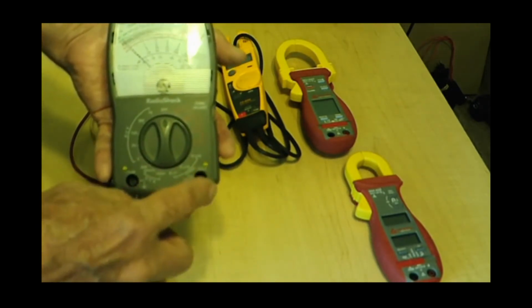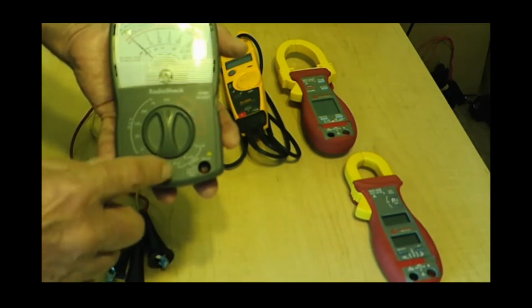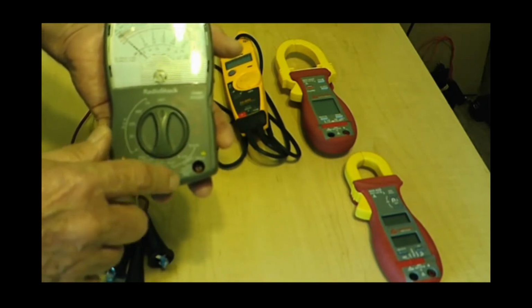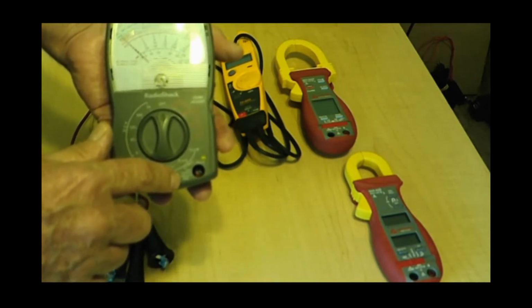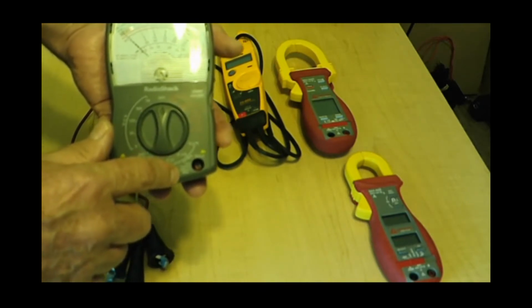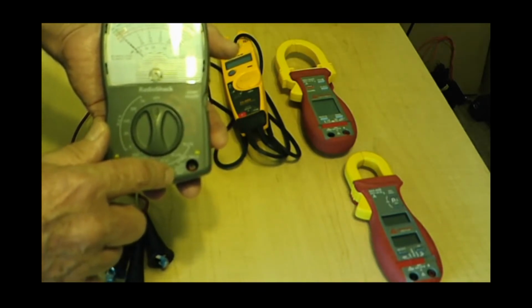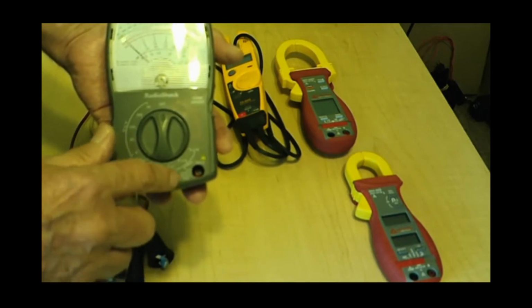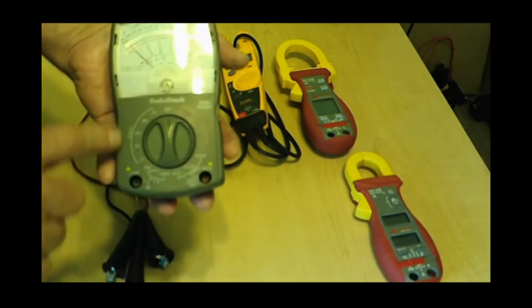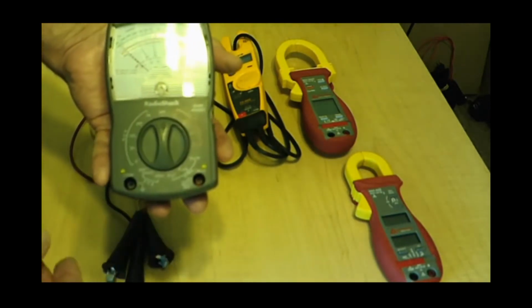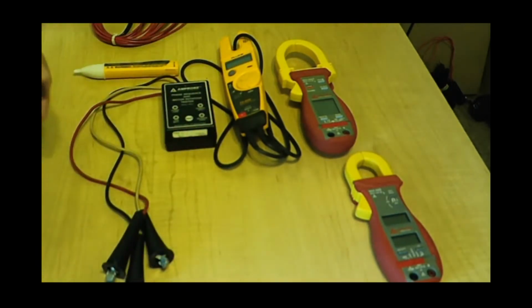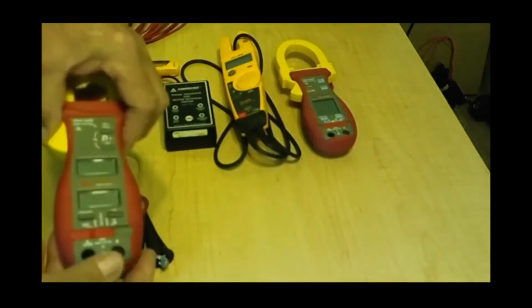You only have two terminals for inputs here. This one is category 2. It's 1,000 volts AC, 250 milliamps max. So the rating's right on there. If you exceed those ratings, this meter can explode. So the ratings on the meter are pretty straightforward and clear.